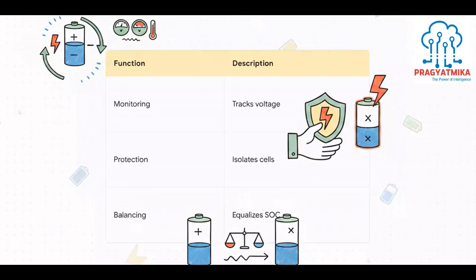Now, what's really interesting about this is how it actually functions. The BMS is constantly monitoring the state of charge, or SOC, as well as the voltage and temperature. If a cell gets a bit too hot or takes in too much current, the protection function immediately kicks in to physically isolate that battery. And perhaps most elegantly, it does this thing called balancing. Because cells naturally degrade at different rates, the BMS actively equalizes the charge across all the cells in a string. This prevents the healthier cells from dangerously overcharging while they wait for the weaker cells to catch up.